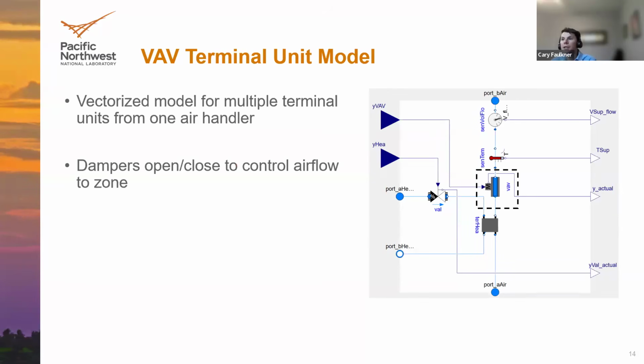So then the first key aspect of this model is the dampers, which is highlighted in the center there. And that's going to connect with the airflow path from the VAV system, as you can see through that blue line. And that's going to include some sort of control to open and close the damper and then model the airflow physics and the pressure flow relationship to determine how much flow is provided to the zones downstream and connect back to the pressure flow physics at the air handling unit.